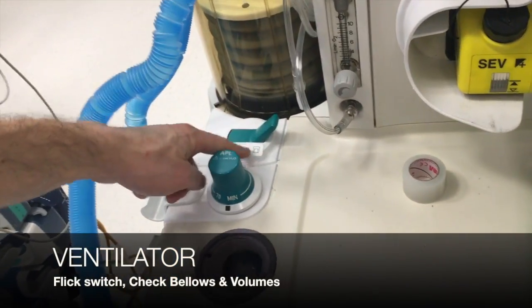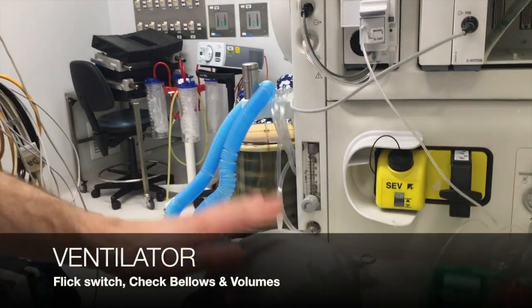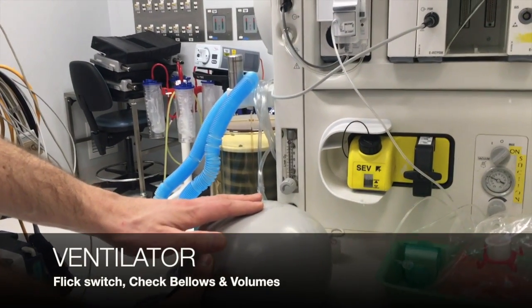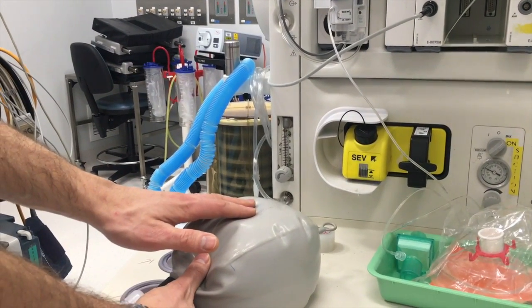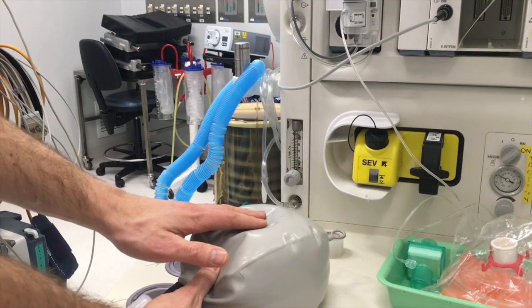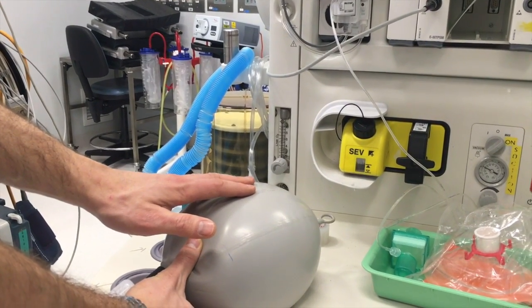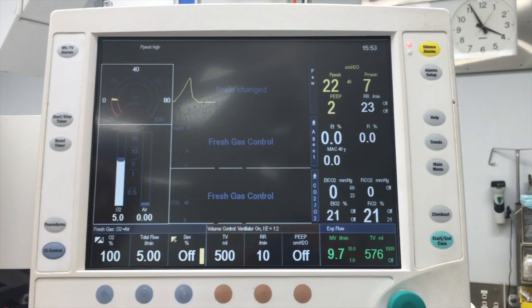Flick the switch to select the ventilator mode and check that the bellows move and the bag inflates. This has all been done with the fresh gas flow still set at 5 litres per minute, and so far there have been no leaks, and adequate tidal volumes and pressures have been achieved.